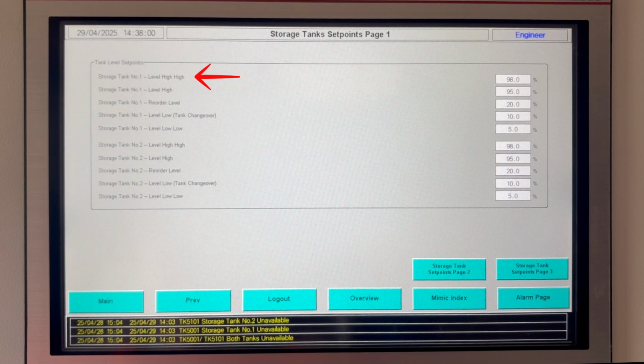Level high will produce an alarm to SCADA and HMI. The klaxon will also sound and be accompanied by an amber beacon illumination. In reality, this alarm state should only happen during a delivery with personnel in attendance and should therefore be acted upon immediately, that is, the delivery to be stopped immediately.